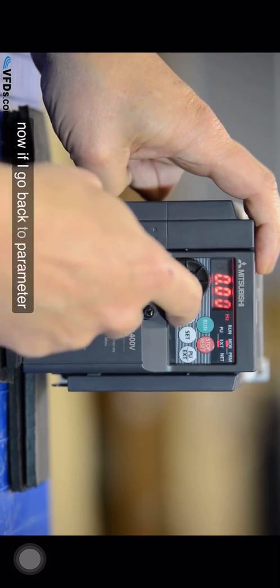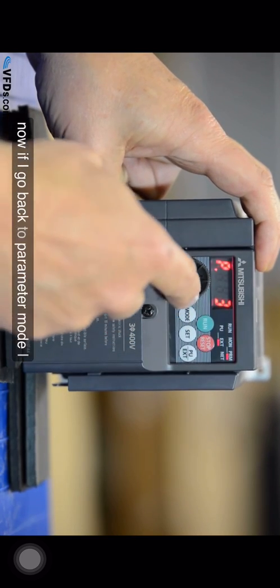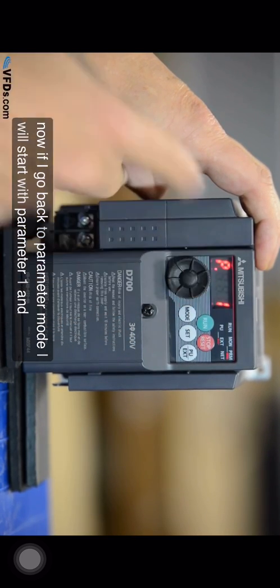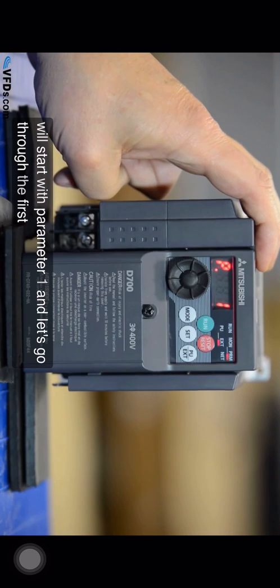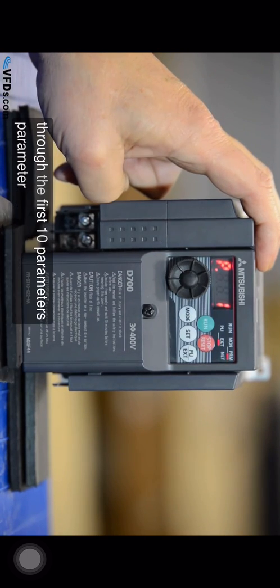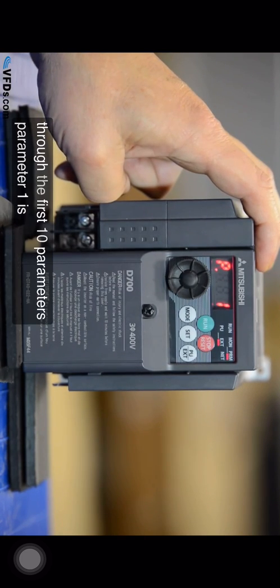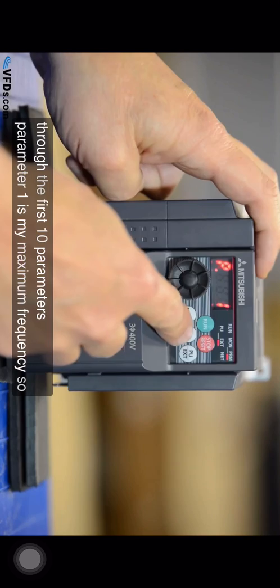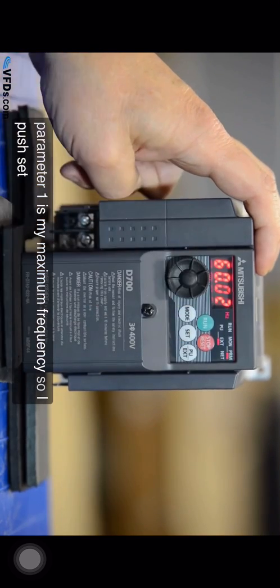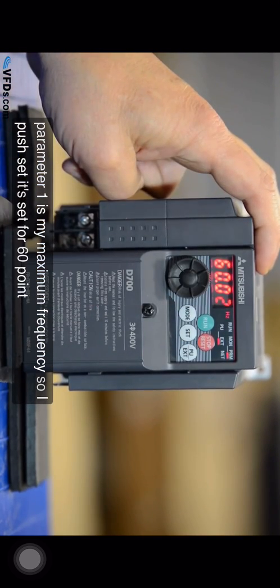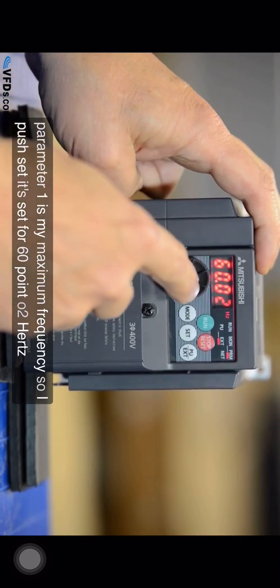Now if I go back to parameter mode I will start with parameter one and let's go through the first 10 parameters. Parameter one is my maximum frequency. So I push set. It's set for 60.02 hertz. Maybe I'd like to allow this to go up to about 65 hertz.